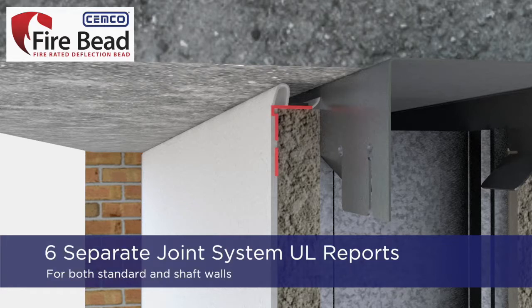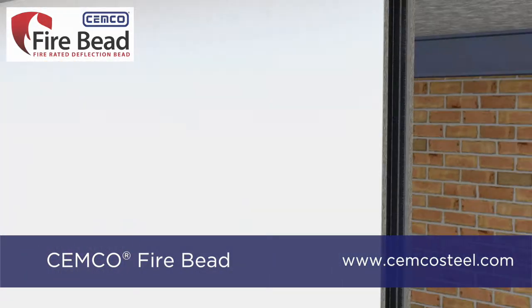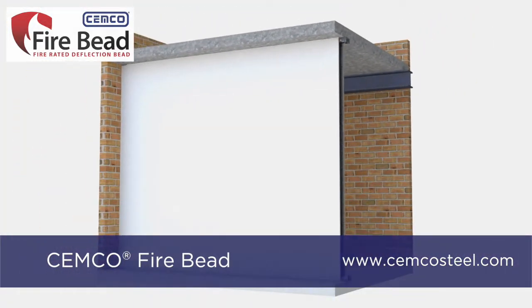Fire Bead has six separate UL joint system reports for both standard walls and shaft walls, and has an L rating of less than 1 CFM for 1 and 2 hour fire ratings. For more information, visit cemcosteel.com.